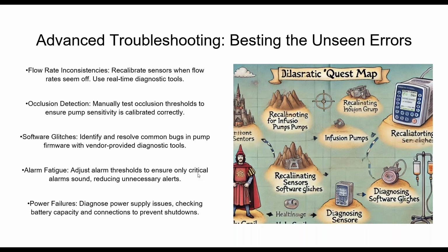And on this, I really should have added this, and I think I may have in another slide, but on your occlusion detections and your flow rates, et cetera, not only check your pharmacy library, but make sure that your pump, if it has a separate batch of settings that can be internally changed, your pump defaults are what your hospital, healthcare system, or clinic has agreed upon, not what the factory defaults are from the manufacturer.